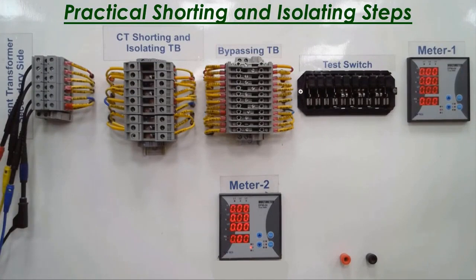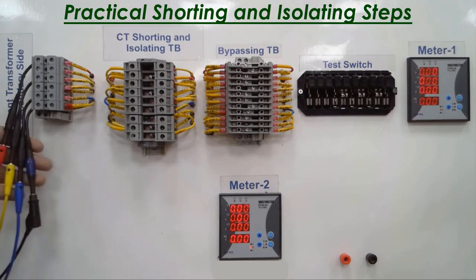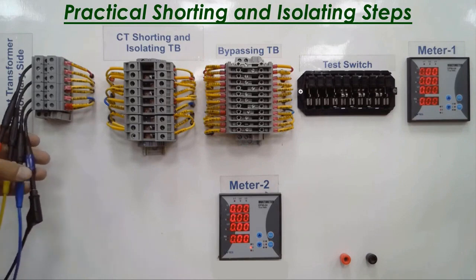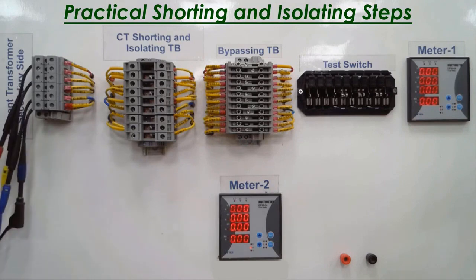Very good. Okay, at the beginning, instead of the current transformer, I will use the current generator output from any secondary injection test kit, like the FREJA 300 or CMC 156. So here I have my 3 phases: red, yellow, blue, and black. Very good. Okay, now I will start injecting 3-phase current with balanced currents of 1 ampere on the 3 phases, with a 120-degree shift between them.